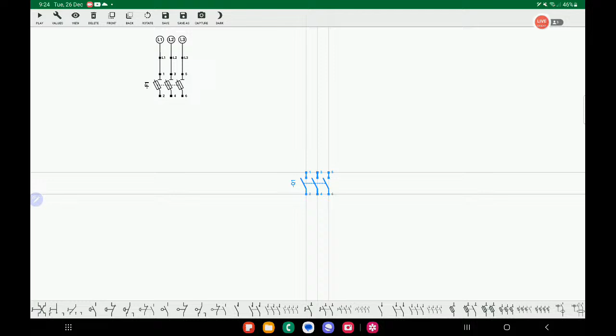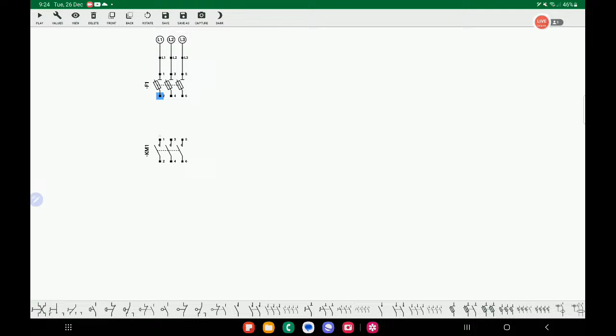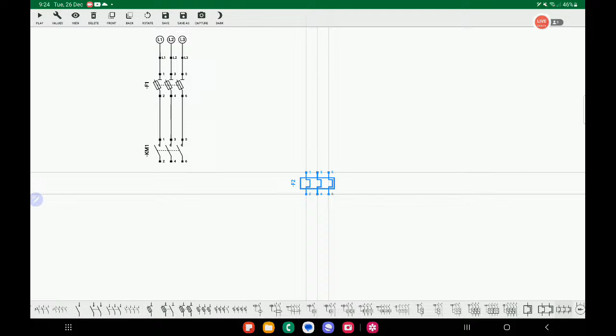Let's say this is F1, the fuse type breaker. This will be the power system of our lifeboat davit wiring diagram. After this we need a main contactor, and then we will put another protection, which will be the overload relay. Then we will put our electrical motor.